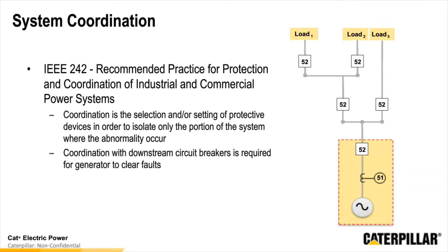The standard also goes on to say that coordination with downstream circuit breakers is required for the generator to clear faults. What this is talking about, as we'll talk through in the discussion today, is the requirement to make sure that the generator itself, as the source, is able to create enough energy or current to reach the downstream loads and to clear the breakers downstream. And so we'll talk about that as we look forward into the discussion as well.